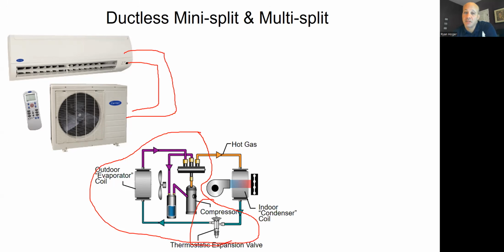So almost every non-mini split, the expansion device is at the indoor unit, and almost every mini split, the expansion device is at the outdoor unit. So that makes a big difference on what I gotta do from an insulation standpoint. So I gotta insulate both lines. So if you're gonna try to reuse existing line sets and you're going from an AC to a heat pump, you probably will have to put a new line set in or go back and somehow get insulation across the old line set, which is really hard because it's anchored to the building in all these different spots. So it's easier just to pull a new line set in most situations. So keep that in mind in the cost scenario that you may have to do that.